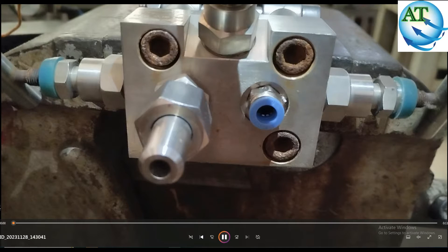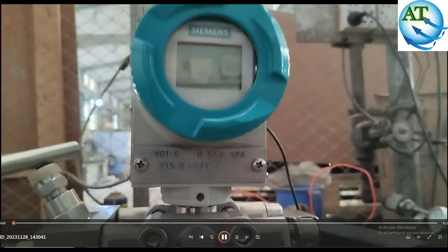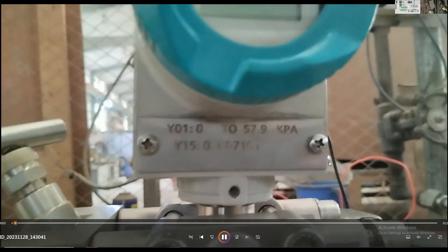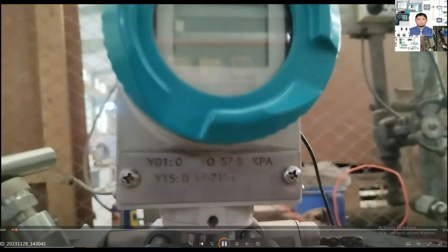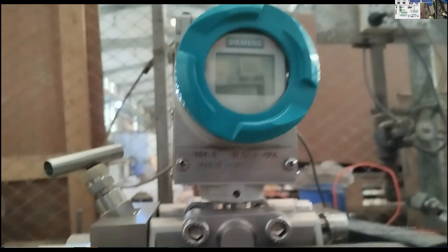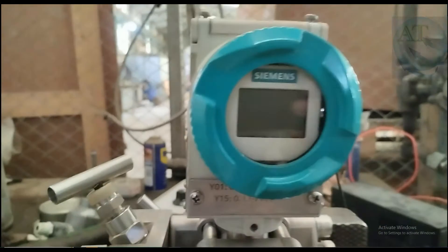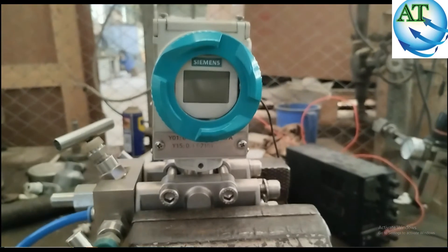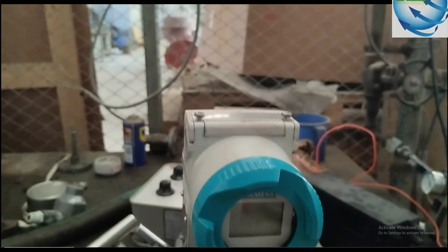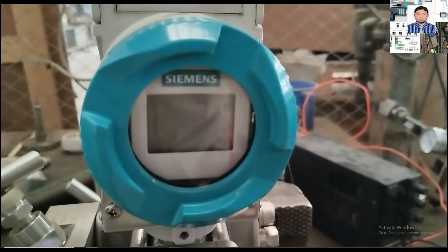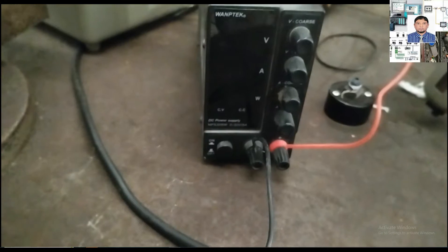First, I am showing the transmitter that we want to check the calibration of. The range of this transmitter is 0 to 57.9 kPa. This transmitter is used to measure the level of a tank by using variable air pressure.